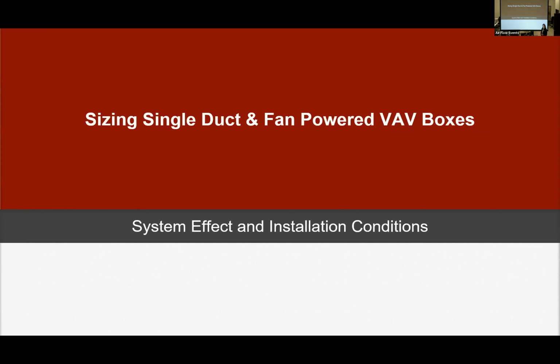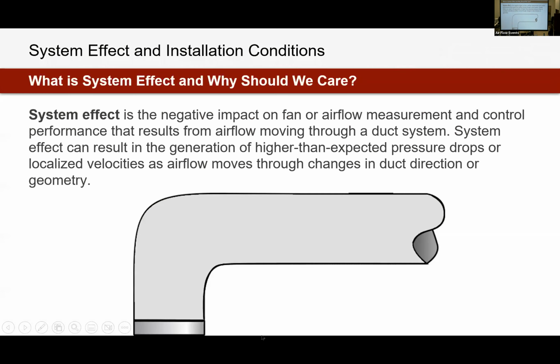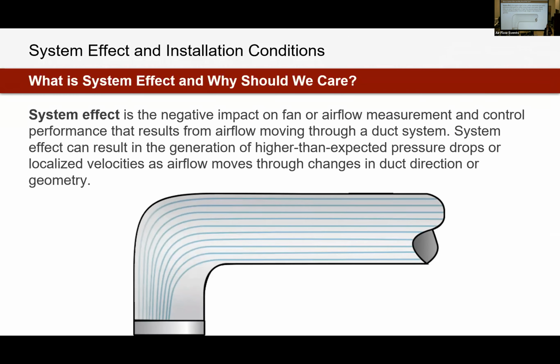All right, system effect and installation conditions. I've touched on this a little bit. The way that we're installing equipment is big and it's important, and it could ultimately affect the performance of the equipment. So system effect as a whole is the impact on our system, on our fan, on our airflow measurement that results from improper movement of air through our duct system. So for an example here, we've got really nice airflow. As soon as we turn that tight elbow, we're going to start getting some localized velocities on one side. This is one isolated example of system effect into a single inlet. But if you carry this for installation through your entire system, those little inconsistencies will continue to have a negative impact on your entire system.